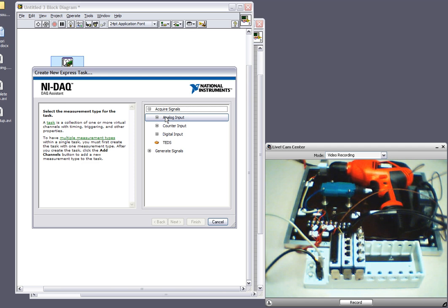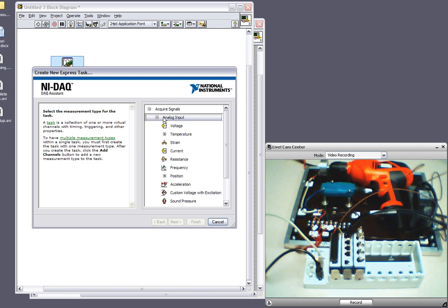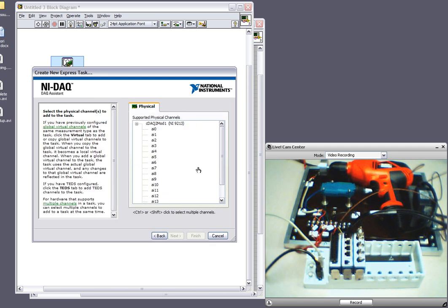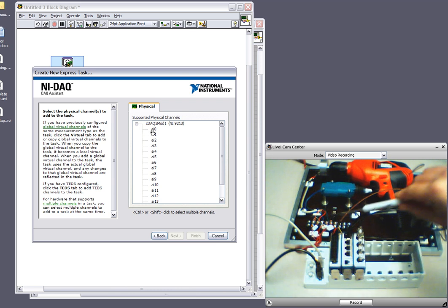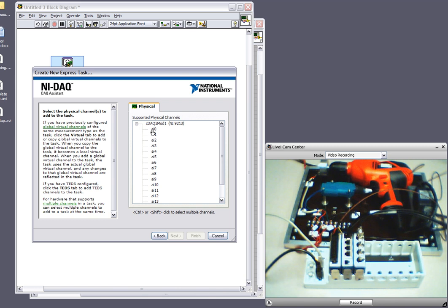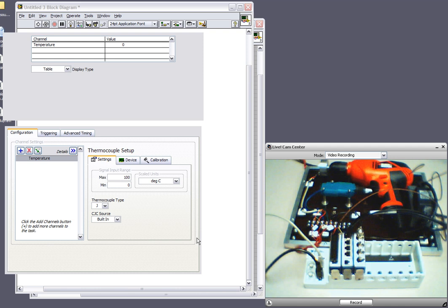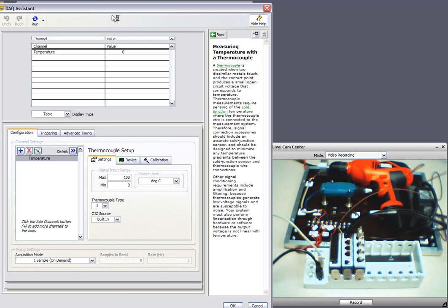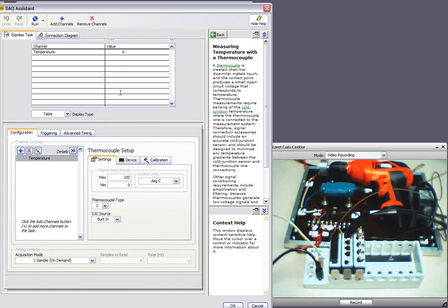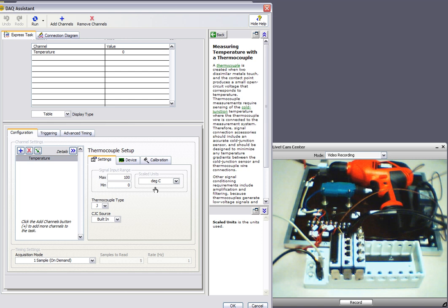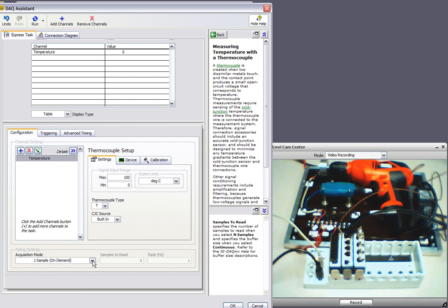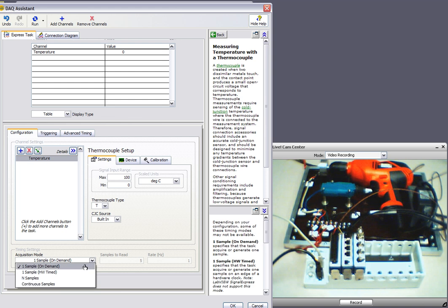So the first measurement I want to take is the temperature. The thermocouple is inserted into the 9213 on channel 0. So here's the DAQ Assistant configuration window. You can see that I'll be taking measurements in degrees Celsius. I need to change my thermocouple type to match what I have, which is type T. And I want to acquire my samples continuously.